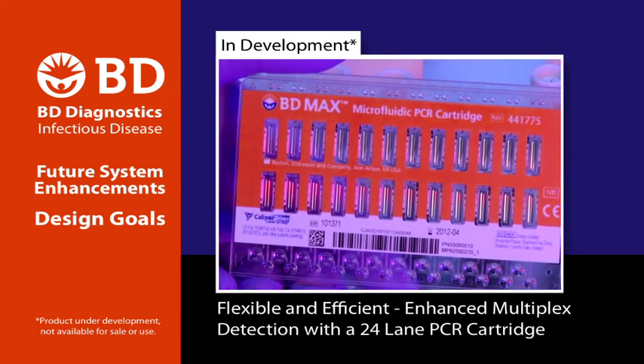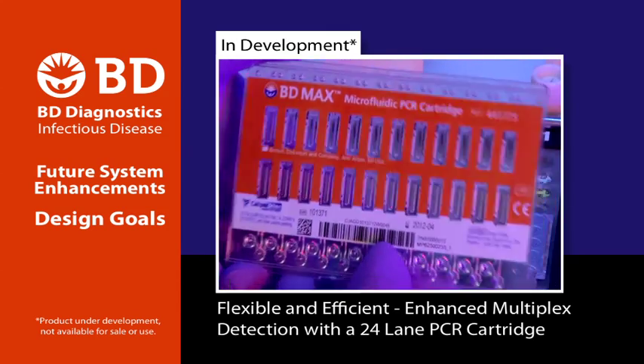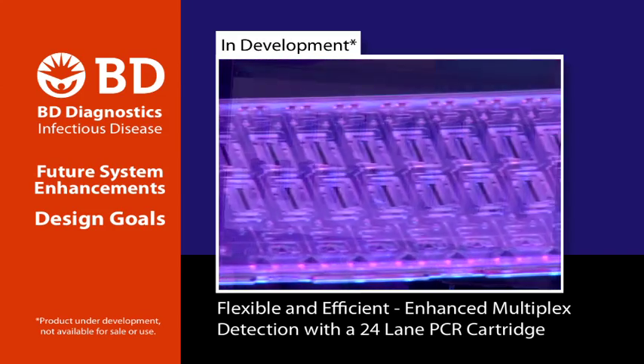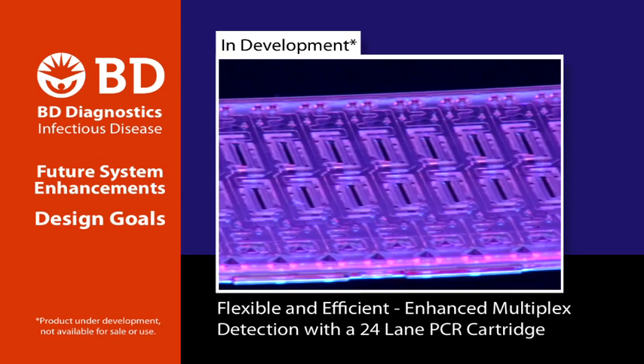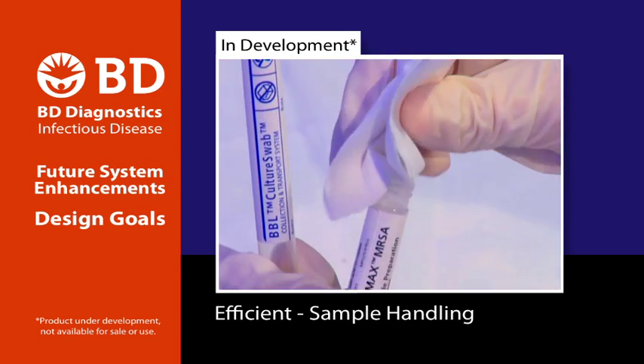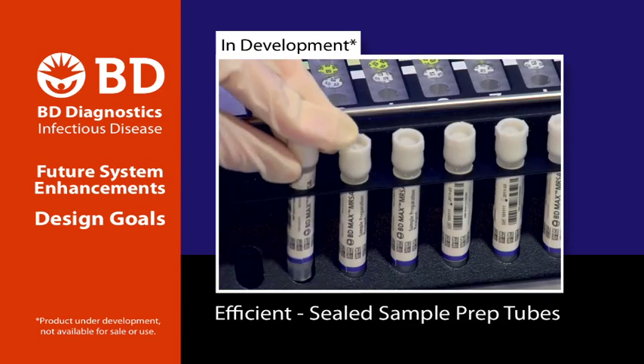Planned enhancements to the PCR cartridge include expansion to 24 lanes or PCR reaction chambers, which will allow greater multiplexed analyte detection capability for the planned future menu. Sample preparation will be more efficient with a specimen swab transferred into the sample prep tube, then loaded on the BD MAX.